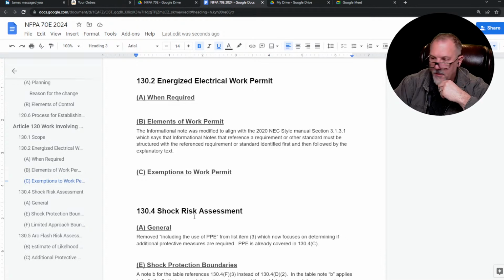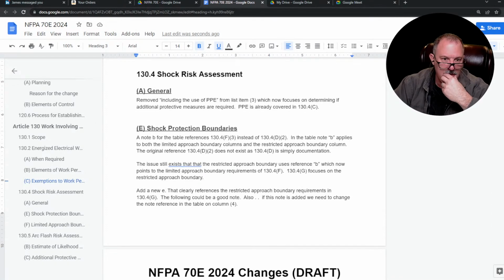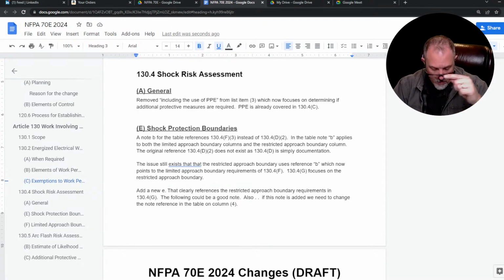Then we got 130.4, shock risk assessment. Include the use of PPE. So in A, removed including the use of PPE from the list, item 3, which now focuses on determining if additional protective measures are required. PPE is covered in 130.4C. 130.4 A, B, C, additional protective measures - that's already covered, that's why they removed it there, so it was duplicate.